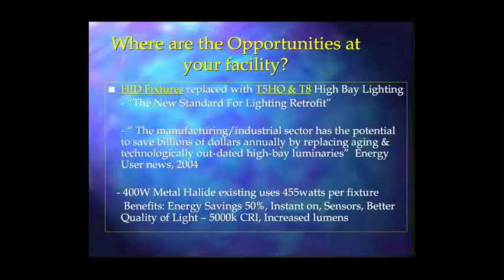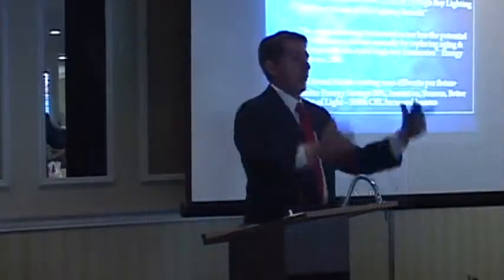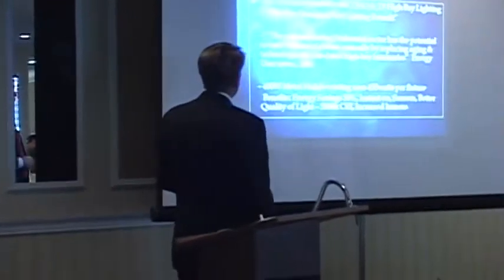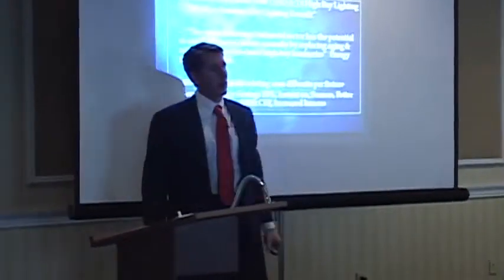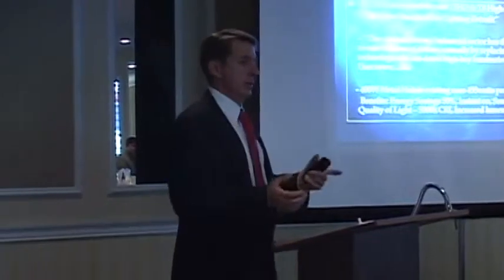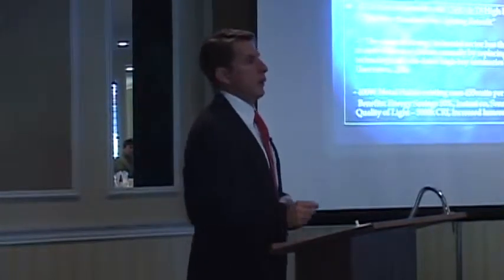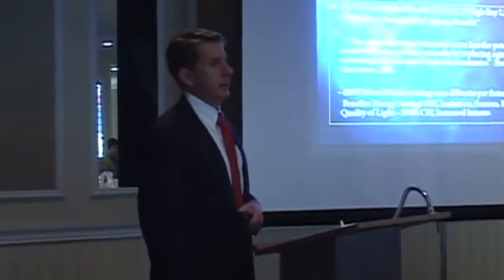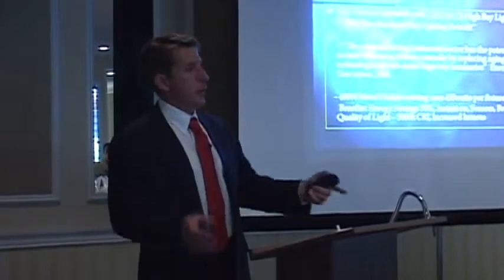There's a huge trend that's taken off in the past 5 years, and BG&E has the best rebate for this specific energy conservation measure I'm about to talk about. I'm sure Pepco will also. Basically, if someone came out and looked at a warehouse that has HID, high-intensity discharge fixtures, which are 400-watt metal halide fixtures that look like the bell you'd see in a gymnasium, or a high-pressure sodium fixture, which looks like a bell and has that yellow light, we can take those fixtures down and replace them with a more efficient fluorescent technology, T5 high output, which is a European technology, or a T8 fixture. That reduces the energy consumption by about 50%, with the same lumen output and instant on. We can put an occupancy sensor on the end of it. I think BG&E's rebate is $75 a fixture, which more than pays for the labor and even part of the fixture installation.